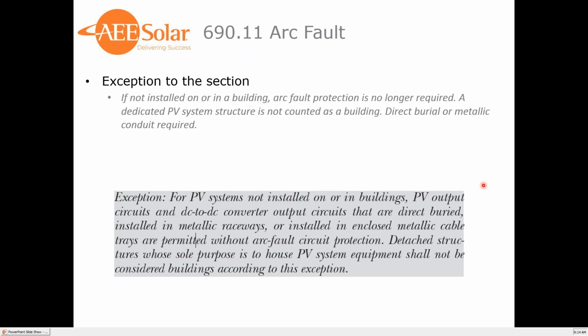So section 690.11, arc fault, mostly unchanged, but now there's an exception. Not really a huge benefit to grid-tied systems because we're required to have arc fault. Probably the biggest benefit will be DC coupled battery-based systems, just because they have limited options for arc fault equipment. Another nice thing is the exception that they put in. If the building is actually housing, like, a power shed to house your equipment, it's not counted as a building, which means that you do not have to have arc fault in it. So a lot of the off-grid or battery-based guys that have all their equipment in a power shed would not be required to have arc fault.